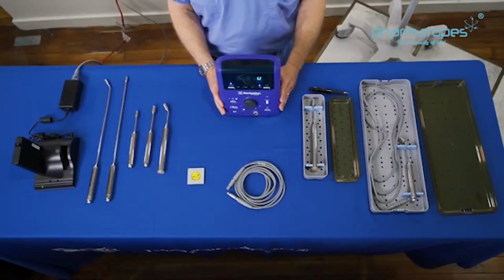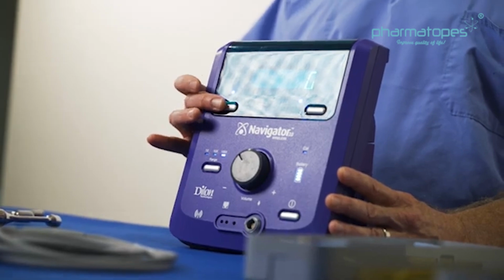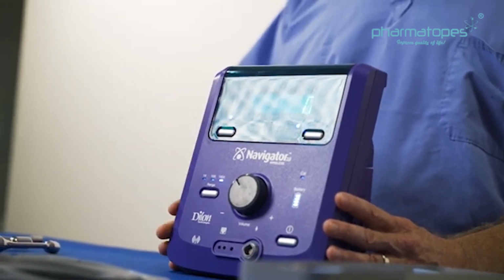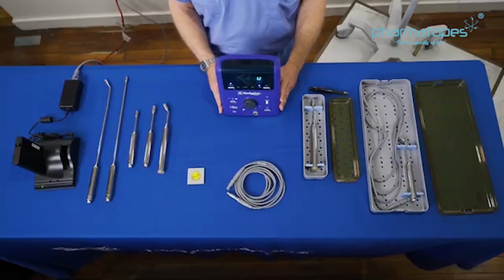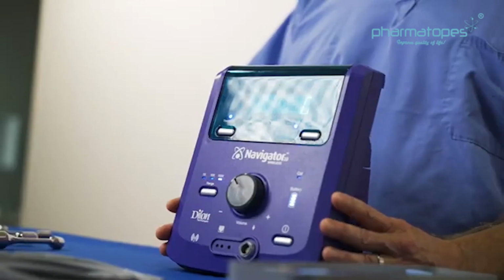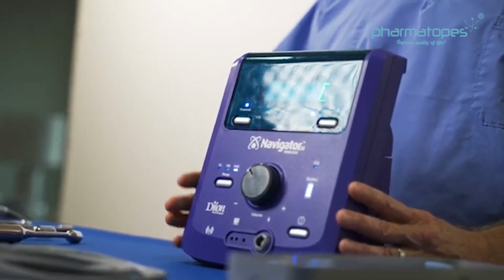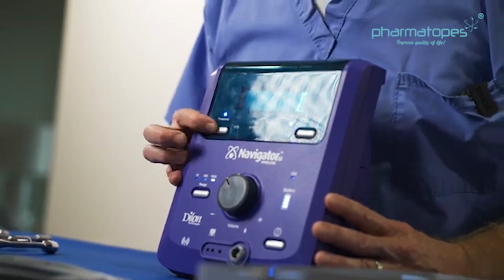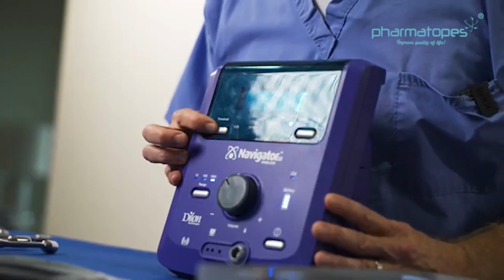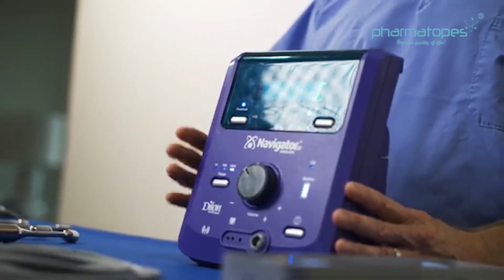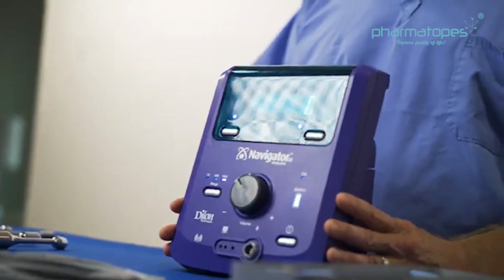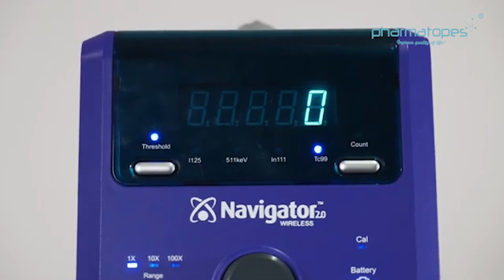to 10 times. The threshold button is for use with only a cabled probe. It controls the count range of gamma energy detected by the probe. When the threshold button is off, the indicator is not illuminated, and all gamma energy, including scattered gamma rays, is detected. When the threshold is on, the indicator is illuminated. In this setting, the detection of scattered gamma rays is reduced or eliminated.